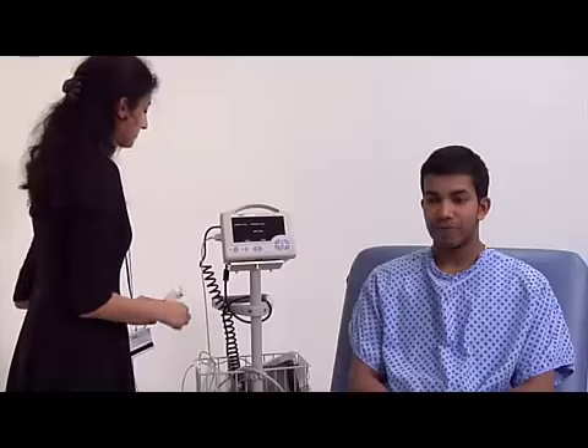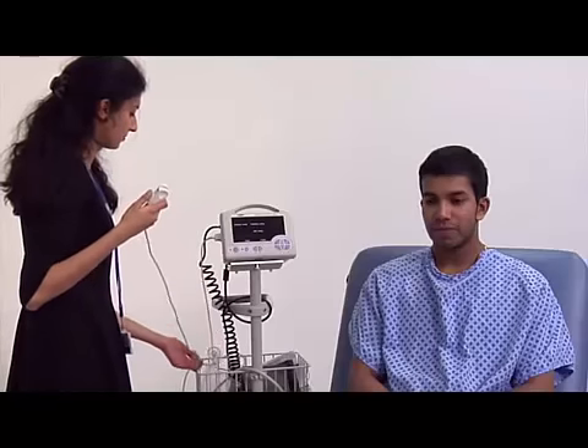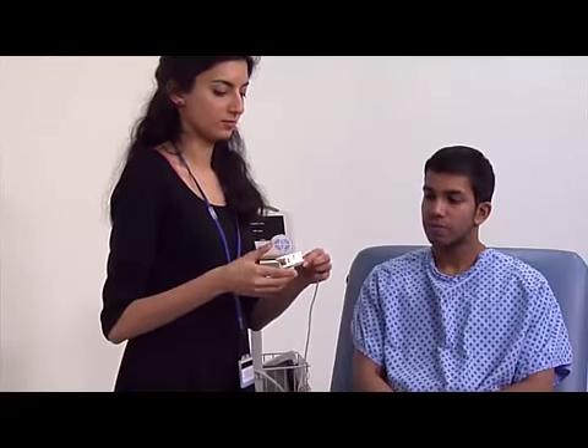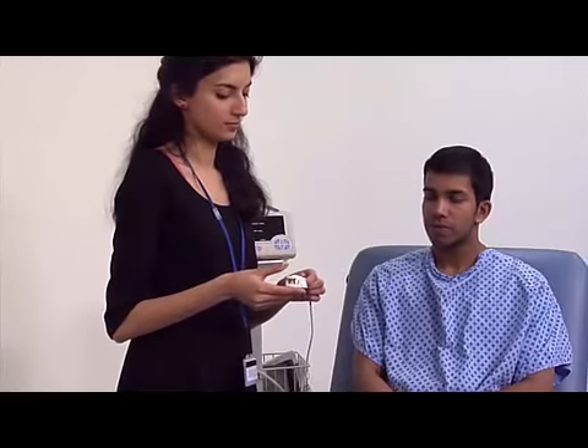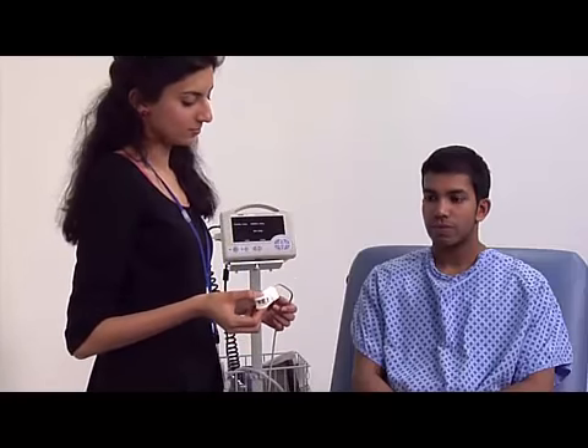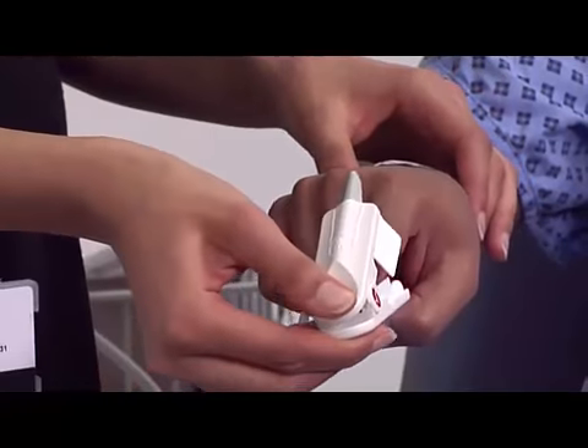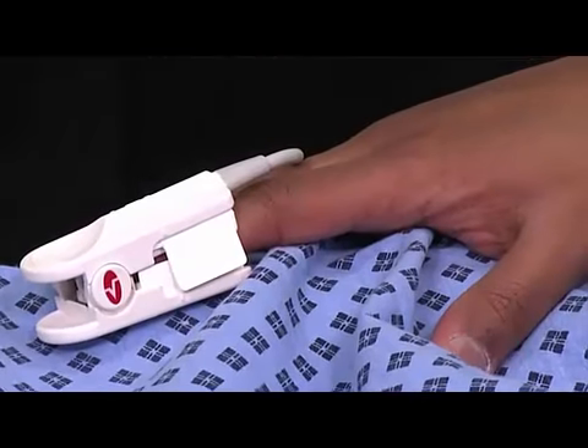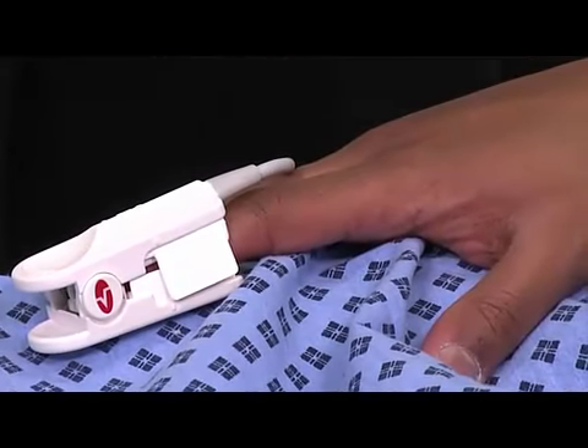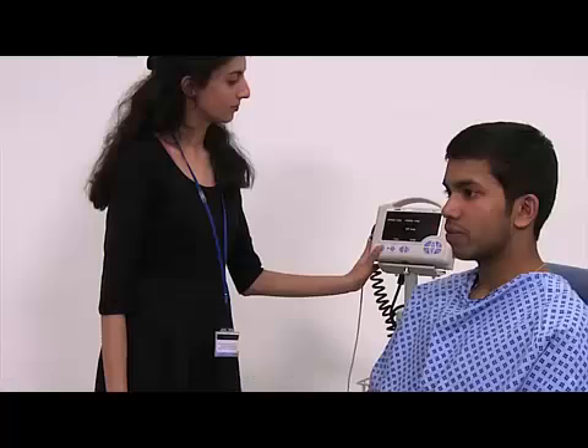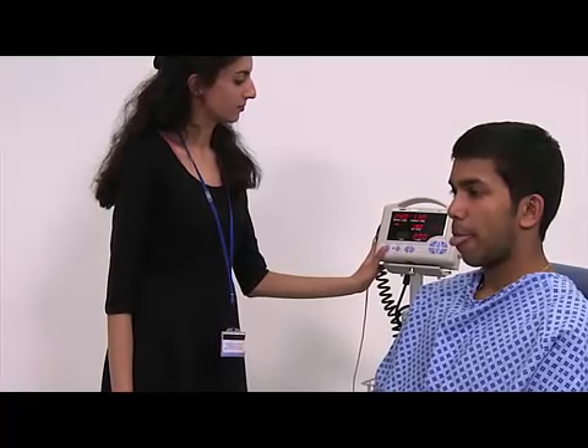If a patient is showing signs of respiratory distress, we can check how well they are oxygenating blood using a device called a pulse oximeter. This is a non-invasive way of measuring the SpO2, which is the oxygen saturation of arterial blood. The device is placed on the nail bed of the finger. The probe should be fitted securely, and any nail polish must be removed, as it can interfere with the reading. The monitor will then display the SpO2 as a percentage.